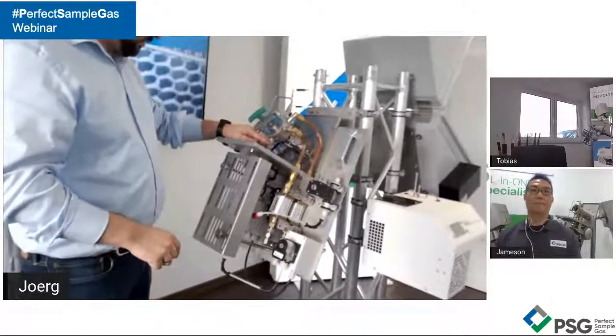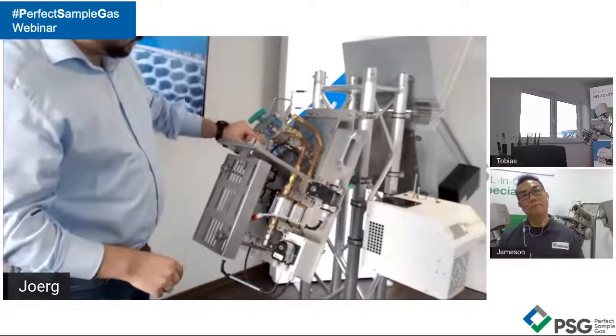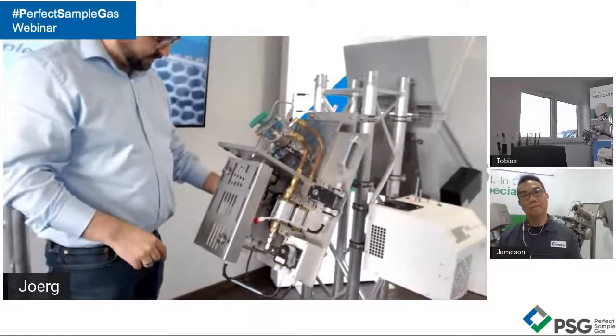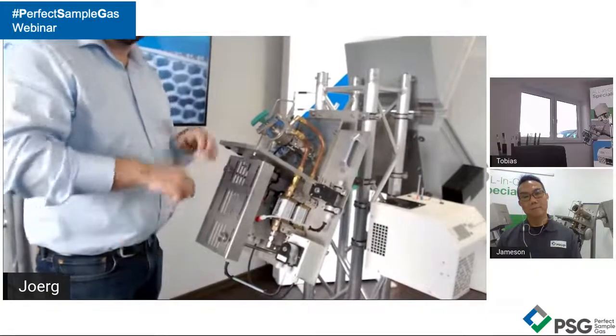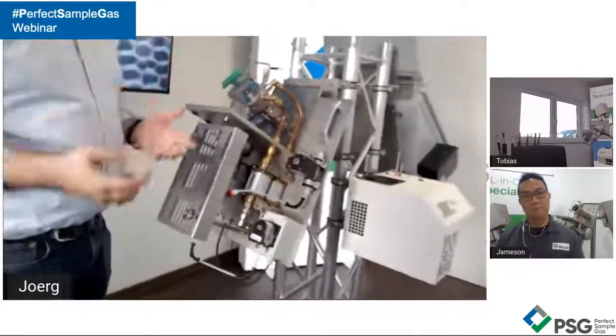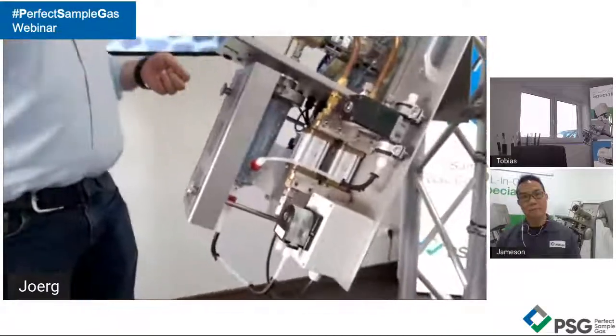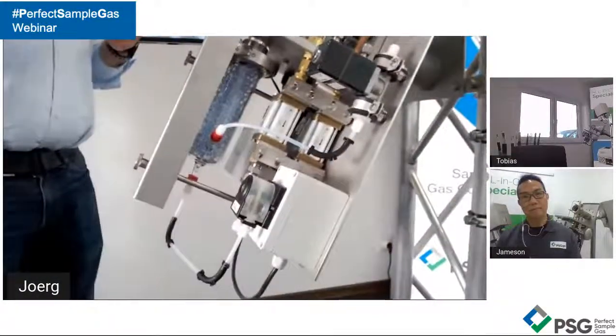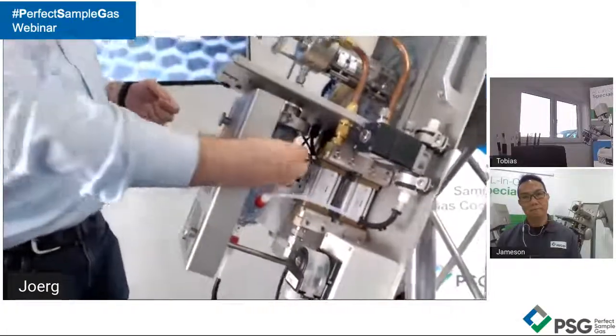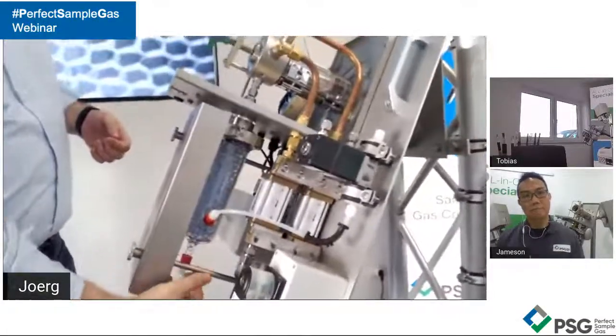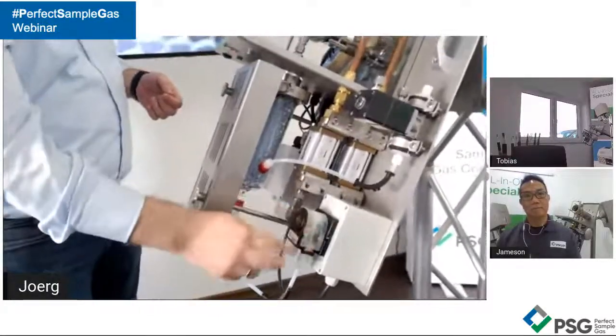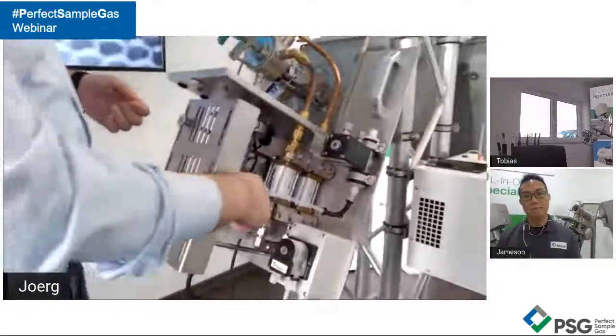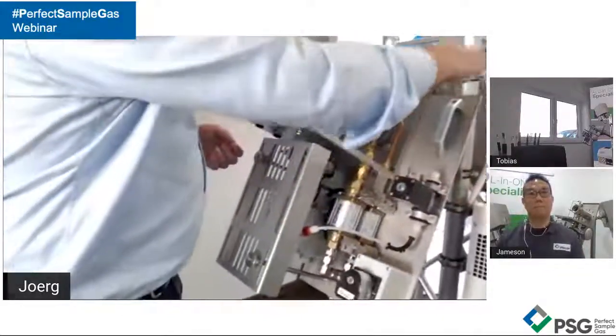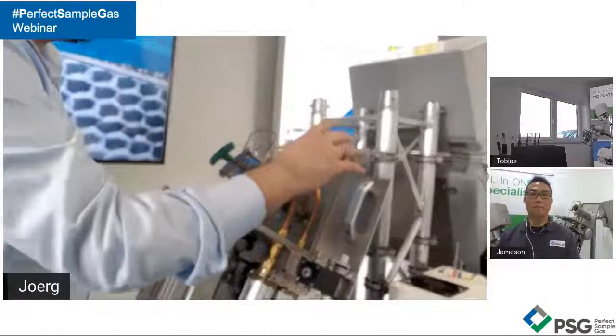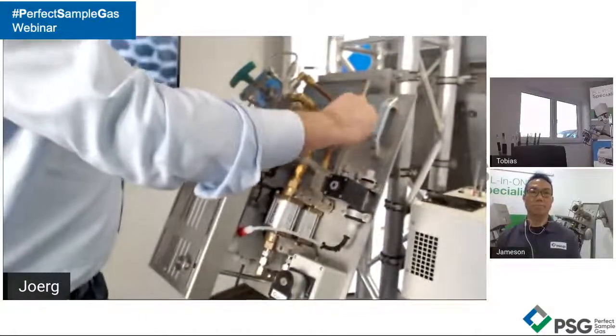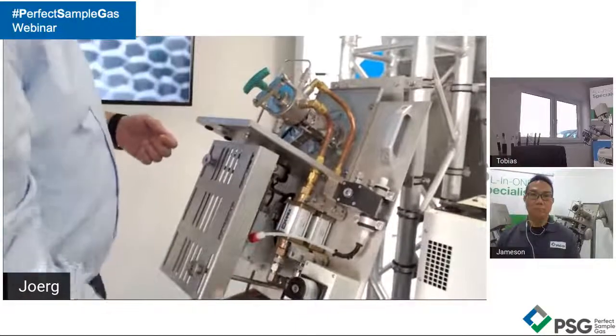What happens after the probe? You want to cool down the medium as fast as you can. So it goes into that distance and into the vessel. The vessel is filled with glass balls to maximize the surface and to maximize this effect. So all kinds of salts that appear when you drop in temperature will form here. After the vessel, there's a big outlet with a peristaltic pump to get the material out. From here, you can continue to a magnet valve and then to a heated sample line with a lower temperature. You don't need, as Jameson explained, because we have already sorted this out.